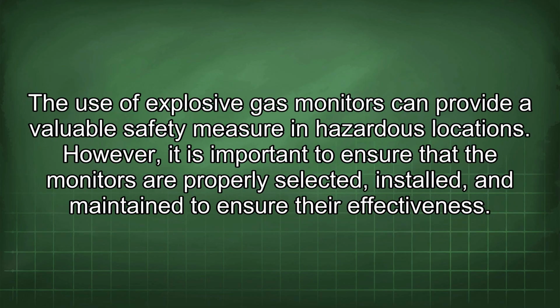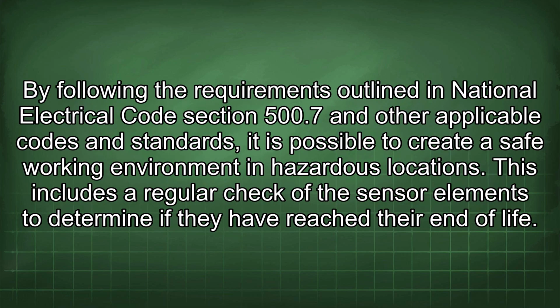The use of explosive gas monitors can provide a valuable safety measure in hazardous locations. However, it is important to ensure that the monitors are properly selected, installed, and maintained to ensure their effectiveness. By following the requirements outlined in National Electrical Code Section 500.7 and other applicable codes and standards, it is possible to create a safe working environment in hazardous locations.